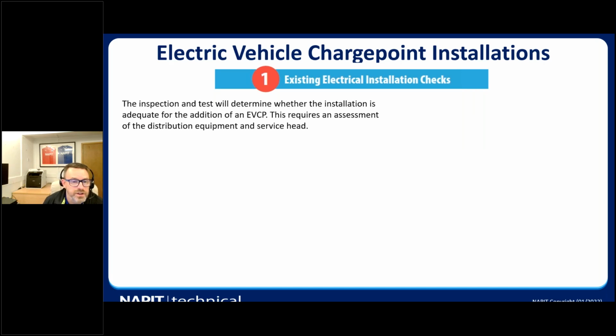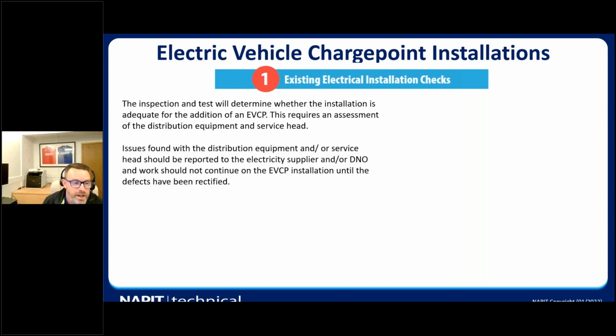The inspection and test will determine if the installation is adequate for an EV charge point, and this includes an assessment of the distribution equipment and the service head, service cables, etc. And any issues found with the distribution equipment or service head should be reported to the electrical supplier or DNO, and the work should not continue until the issues have been corrected for the EV charge point to be installed.